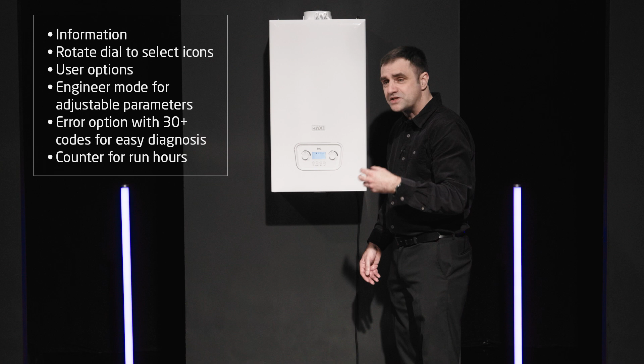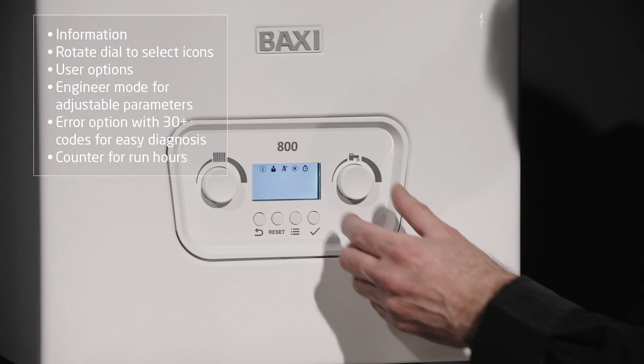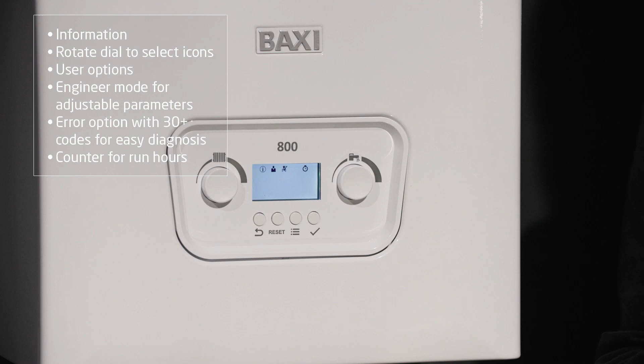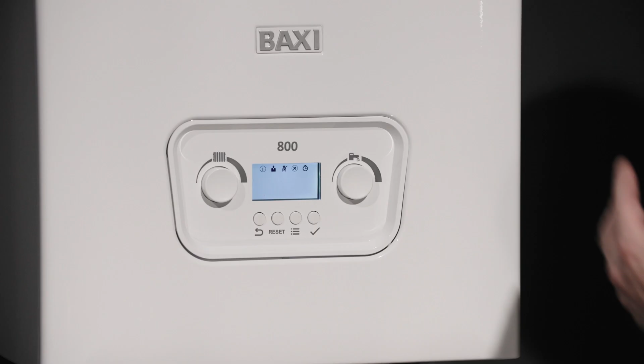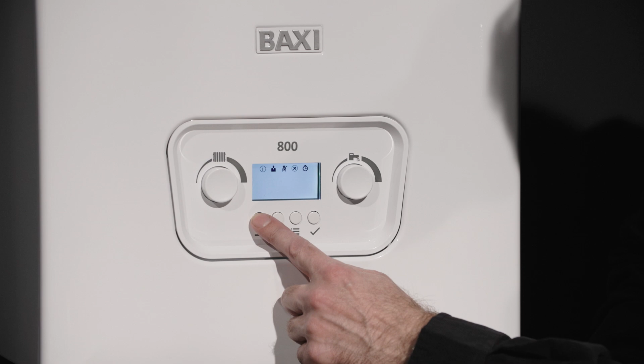I scroll it one more time, and now I'm into engineer mode. Now, if I accept that and go into that mode, what that gives me access to is all the parameters that I might need to change, for example, weather comp, or maybe flow temperatures. Once more, and now I'm into error codes. This unit will store over 30 error codes. So if you're going to a boiler and you're not sure what's been going on, you can look there and you can get that more information to help you better diagnose the problem. And then the last one, that's a counter. That's going to tell you run hours. So how long the boiler's been on for hot water, for heating, or maybe for frost protection. If I want to come out of that menu, I simply press the return button.